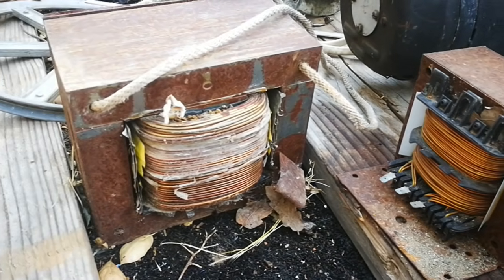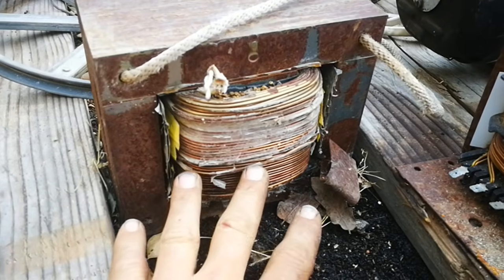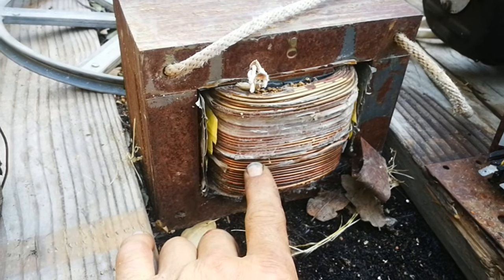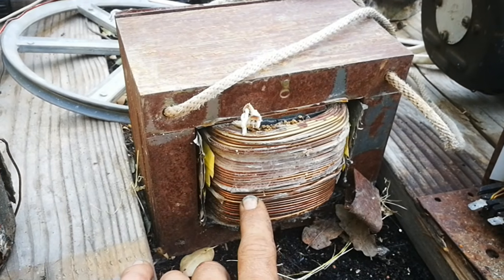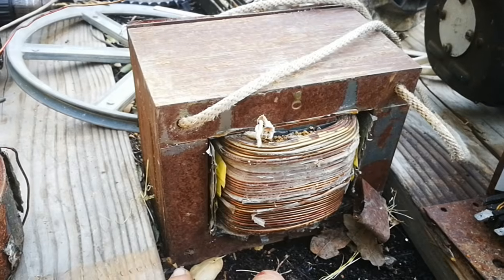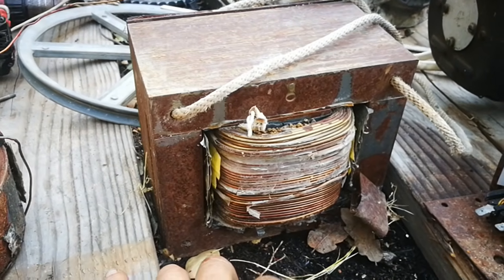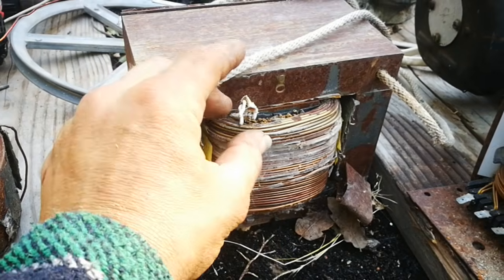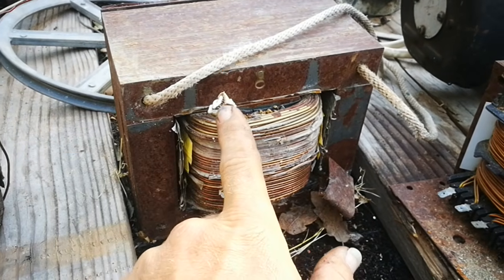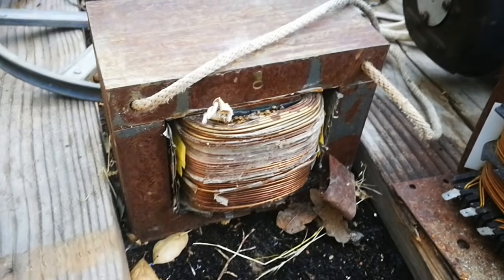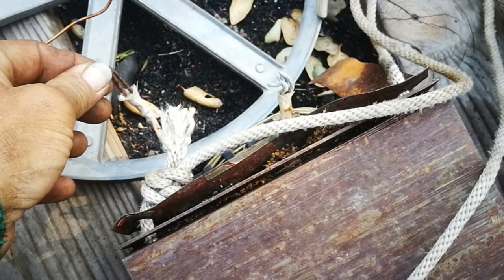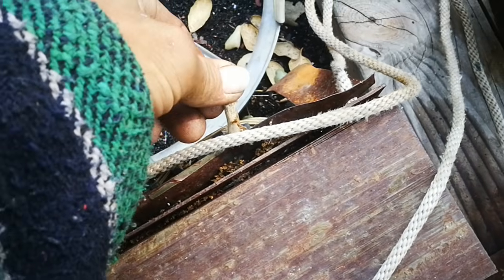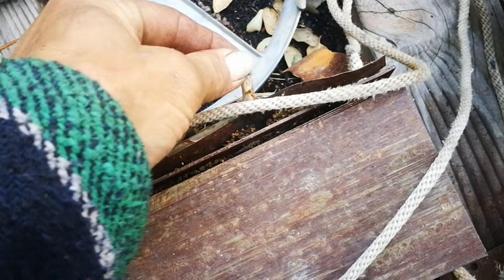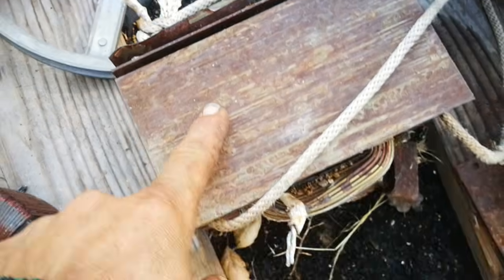Now, some transformers don't have two coils, they only have one, like this one. This is a step up, step down transformer from 120 volts AC to 240 volts AC, or from 240 down to 120. It's a single coil of wire, but made up of two wires wound together as one coil, with three connections: one end of the coil, the other end, and a middle tap wire connected to the very center of the coil as it's wound through all the metal plates.